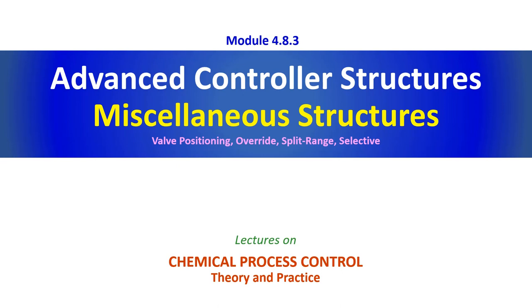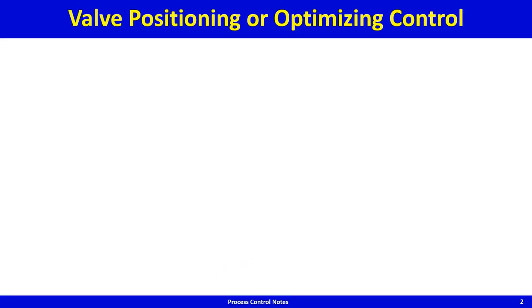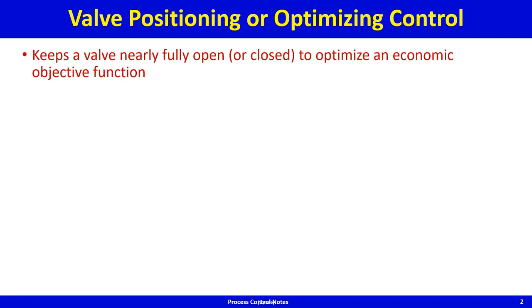Let's get straight to business. Valve positioning control is also called optimizing control because many times running the process at a nearly fully open valve or a nearly fully closed valve is economically beneficial. So valve positioning control is that control structure that keeps the valve nearly fully open or closed to optimize an economic objective function.